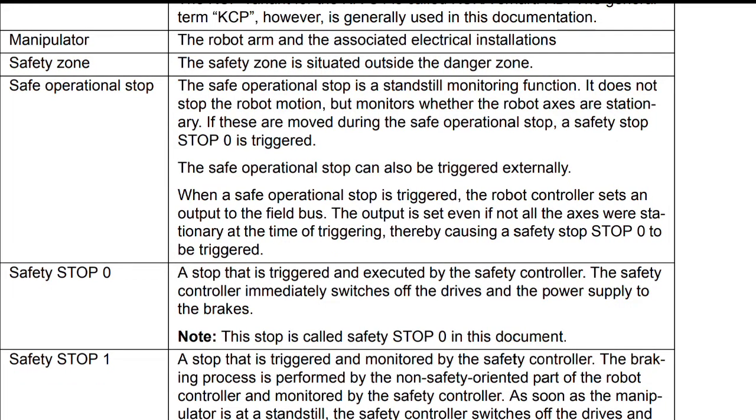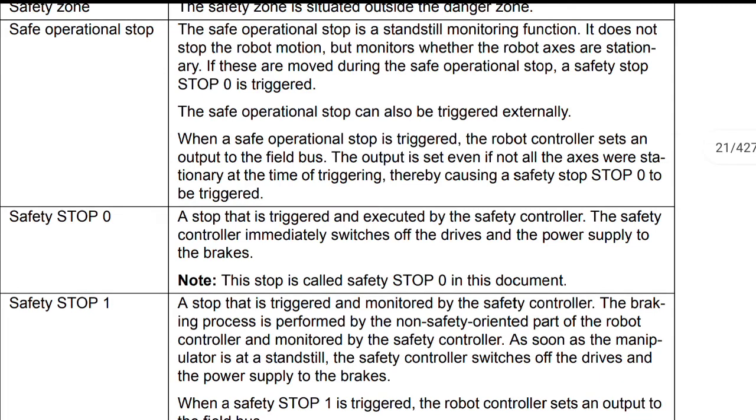Safety stop 0, a stop that is triggered and executed by the safety controller. The safety controller immediately switches off the drives and the power supply to the brakes. Note, this stop is called safety stop 0 in this document.